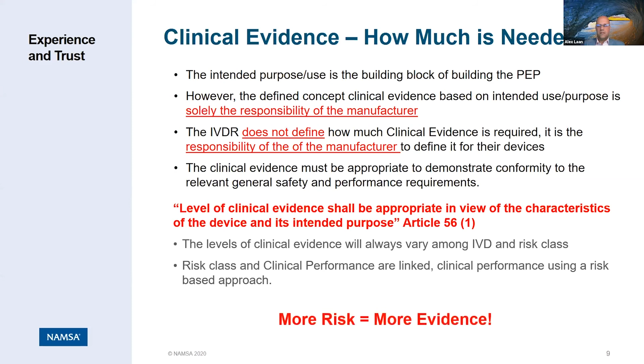Let's say you would have a very novel new device, which is classified as class B, that may perhaps require more clinical evidence because it's new and in the eyes of Europe, more risky than, for instance, an established class D device. So it's not always so black and white. Use your common sense. Risk class and clinical performance are linked. Clinical performance using a risk-based approach is very sound. More risk in general means more evidence.